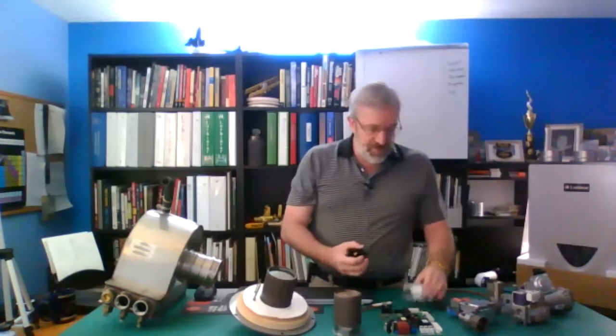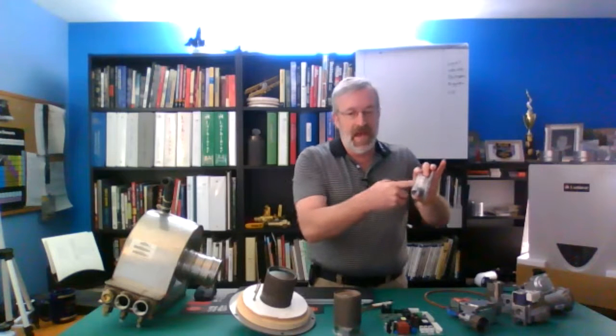As the air moves through the venturi, it creates negative pressure on the orifice. That suction is pulling the gas in through this opening on the outer side of the inner venturi, if you will, and the orifices, down into here, into the fan, down into our burner. We get our combustion. So that's just a quick look at how that negative regulation works on that end of it.